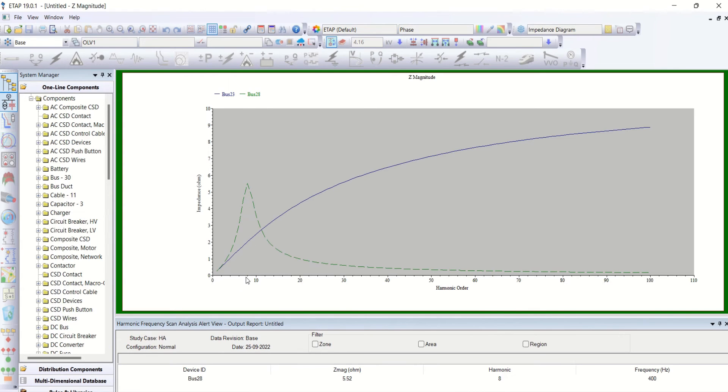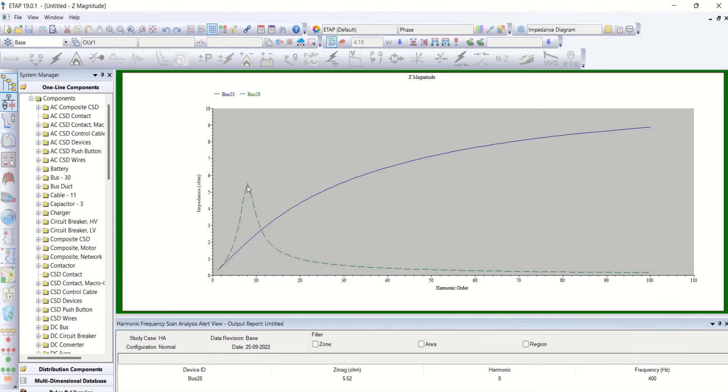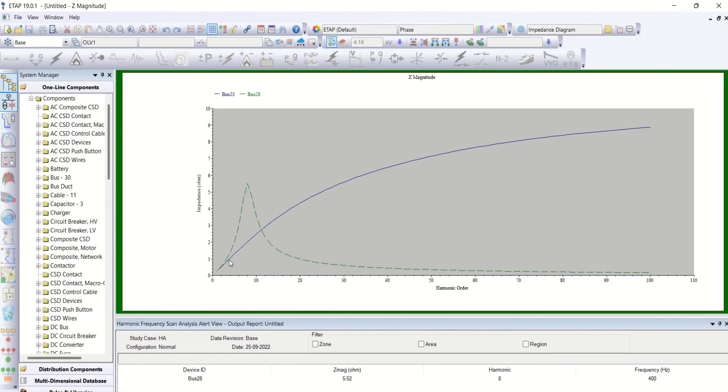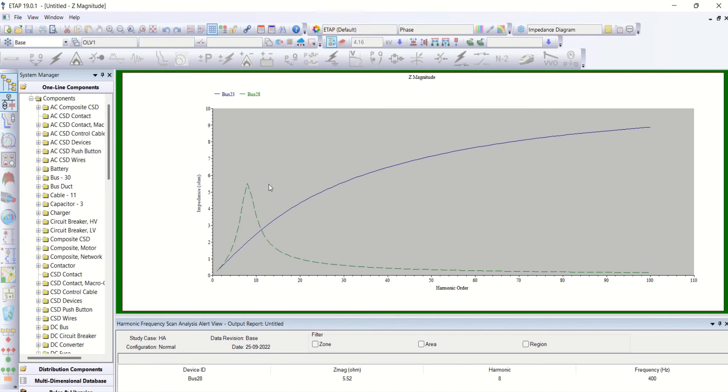Approximately you can see about 8 or 8 or 9. Around this order you may have parallel resonance. Parallel resonance means impedance becomes high, admittance becomes low. So that is creating high amount of harmonic content in the system.